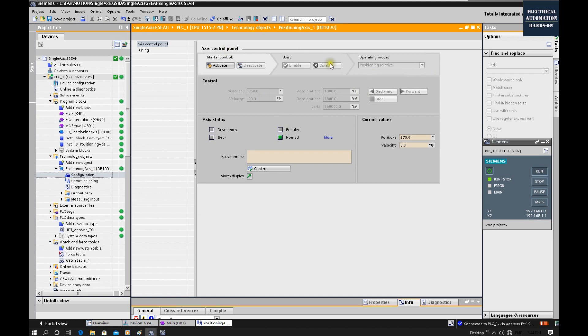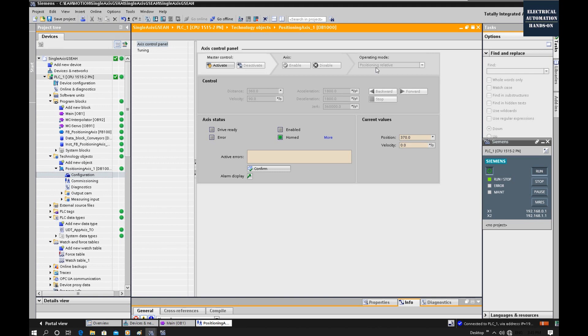Using this control panel, we need to verify the forward and backward direction, verify the actual speed, if the speed setting makes sense for this machine. Also, we need to verify the home position and the positioning, the mechanical relationship between our setting and our actual load travel distance.